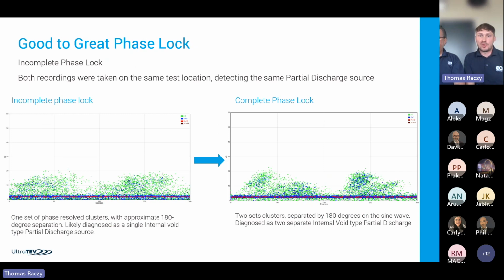Okay, another example. Again, on the left-hand side, we've got incomplete phase lock. So we've got a bit of a buildup of a phase resolved pattern, and it looks a little bit like PD. We can just about tell that there are some groups within this on the screenshot, but it's not very clear. That could happen in a real-life situation, for example, if we're triggering the lights and the light source is behind us. If we start casting a shadow on the photosensor, the instrument might lose the phase lock. On the right-hand side, we've got complete phase lock, and that enables us to carry out a detailed analysis.